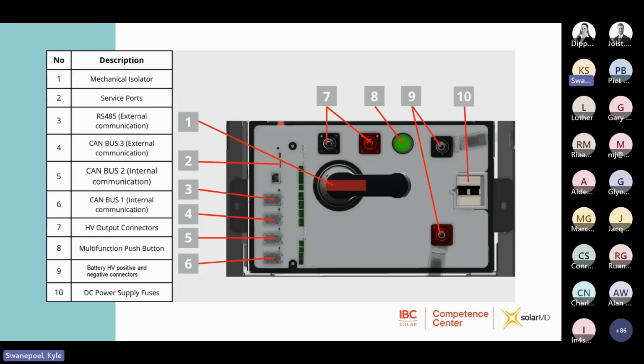All right, so just a closer view of what the BMU looks like and its functionality. Number 1 is your mechanical isolator. This is a mechanical disconnect, which will break the positive circuit. Then we have service ports. This is essentially just for service related and R&D things. Then I'll cover all of these together. The battery comes with internal CAN bus communication, which will be your CAN bus 1. CAN bus 2 is inter-battery communication, so this is between BMU and BMU. And then CAN bus 3 and RS485 is reserved for communication to your external inverter.